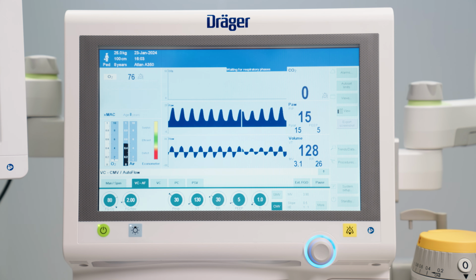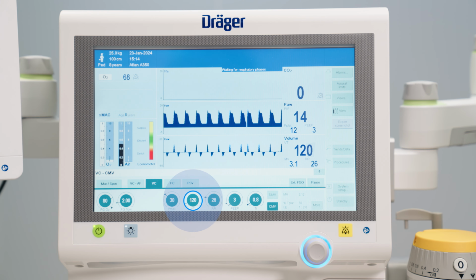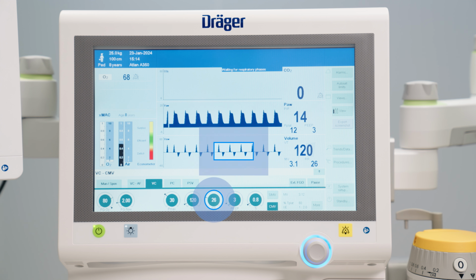Smaller children are ventilated with higher frequencies, which can result in very short inspiratory times. Especially the minimum expiration times which are needed to avoid air trapping can lead to very short inspiratory times. Therefore, to deliver the set tidal volume during this short inspiration time, anesthesia ventilators should be able to provide high inspiratory flows, enabling high respiratory rates.